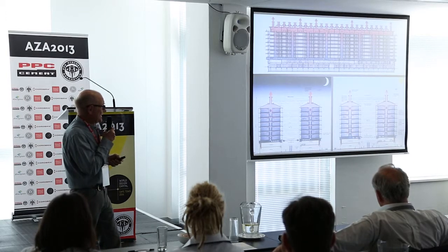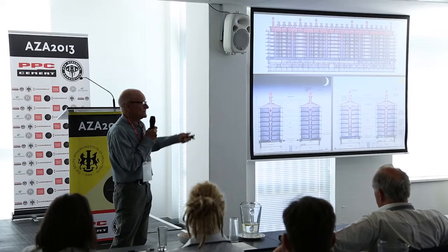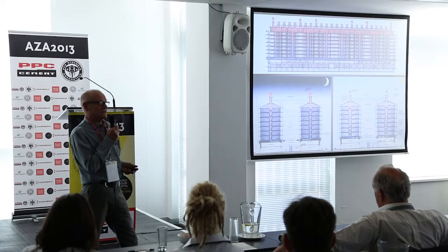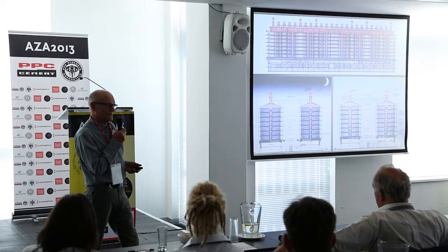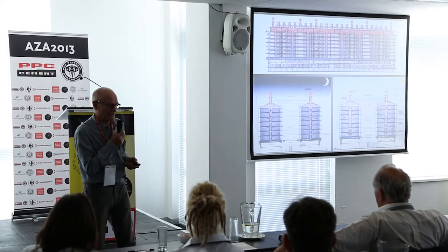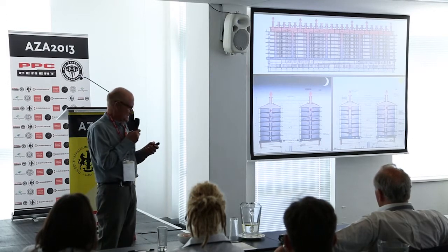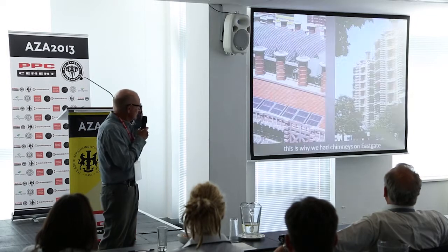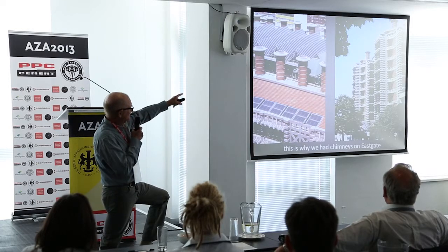And we just have two fan speeds. We have a day fan speed of 2 air changes, and a night one of 10 air changes. We push air through the building at a much faster rate. That cools down the structure, and we use the structure as a thermal sink, which you all know.